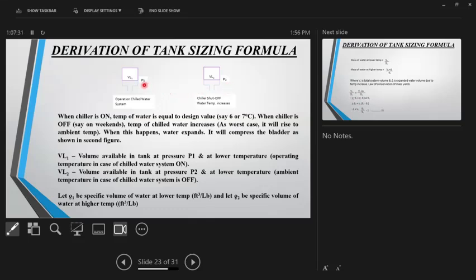P1 was the pressure when the system was running. When the system was switched off, the water will actually push this surface up, correct? So this was the air volume or nitrogen volume. When the temperature of the system increases, or when the chiller system shuts off, I should have drawn this line slightly up so that this VL2 would have been less.